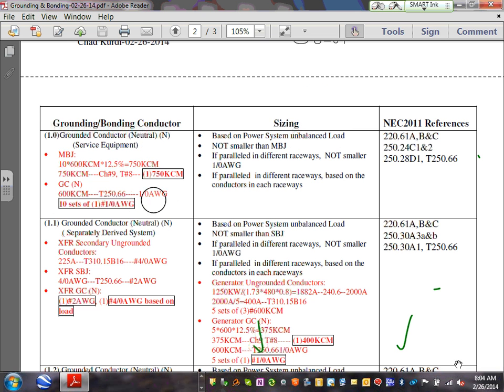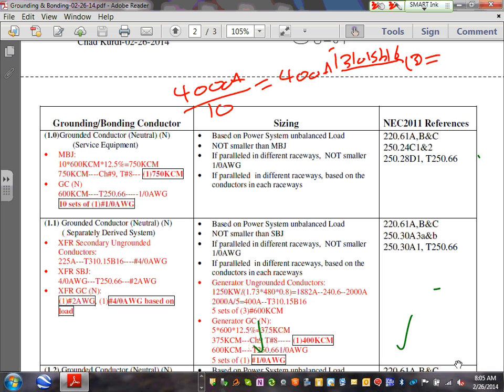Okay, Karen, to size a grounding conductor, the first thing: I have a 4,000 amp switchgear divided by 10 runs. That will give me 400 amp. Can you see? I have 400 amp. If you take it to 310.15 B16, that will get you 3 conductors, 600 kcm. So that's how you size the service conductor. These are the 3-phase conductors. You size the 3-phase conductors first, 10 sets. That's your size, guys. You did that one for me, right?